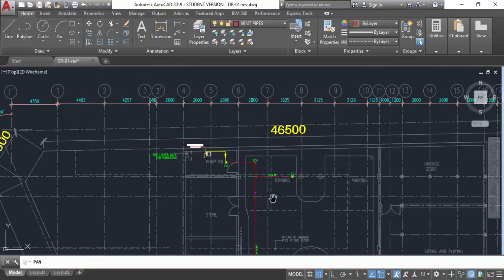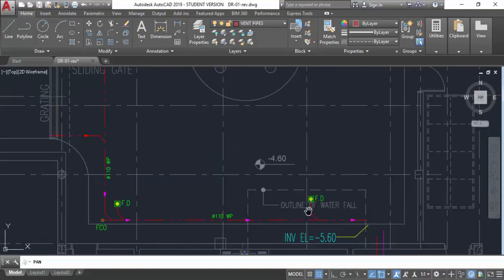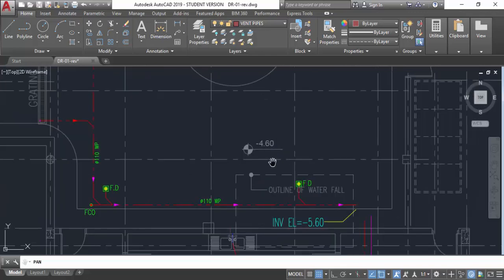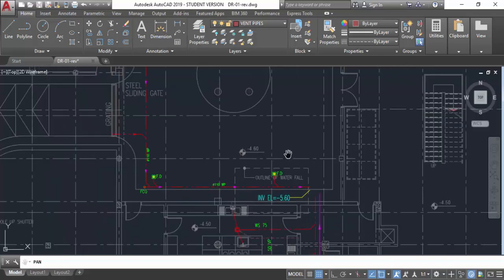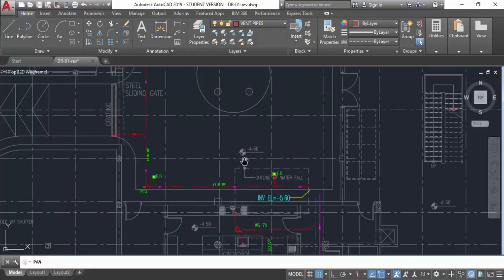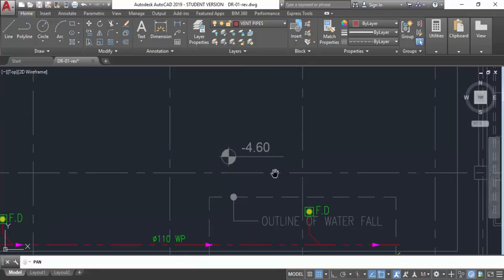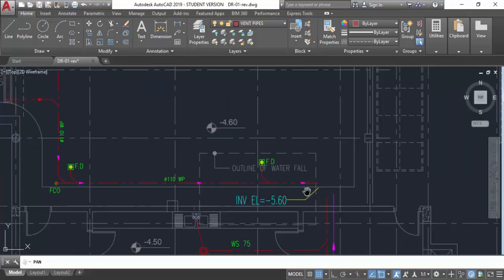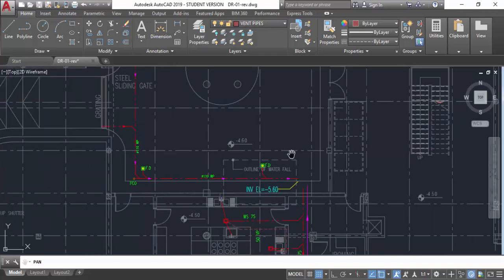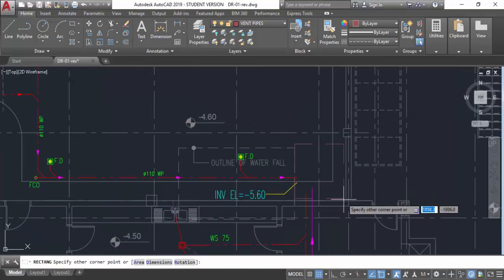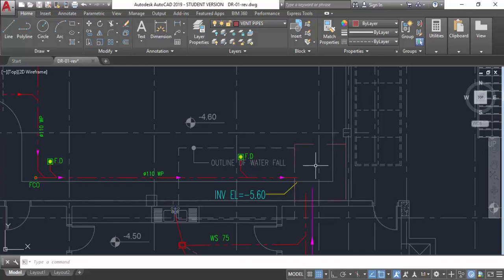We are working in the basement. This basement is 4.6 meters down from the finished floor level — ground level is zero, and 4.6 meters is below that. Because of this depth, we cannot drain the water directly to the manhole; we must pump all the water out. So we have to provide a sump pit and pumps. We need to provide two pumps: one working pump and one standby pump in case the first pump fails.